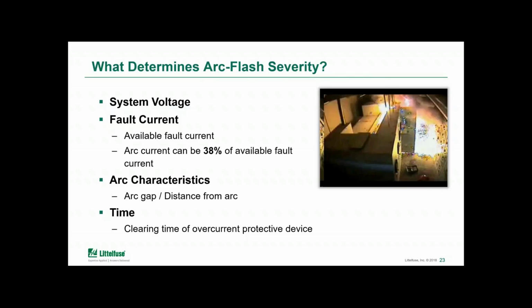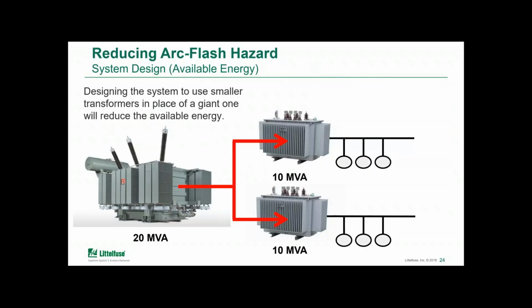Now, if we're looking at retrofit, that leaves time, which is the focus of some of the engineering controls for arc flash mitigation. Now, in terms of design phase, one way to reduce the energy that's available to a fault is looking at a flatter topology. In the example here, we're showing a 20 MVA transformer, and instead of using that, perhaps two 10 MVA transformers could be used to feed the two separate buses. Now, of course, if the design calls for a link between them, then the arc can be fed from both directions, and so that would not have the intended effect.